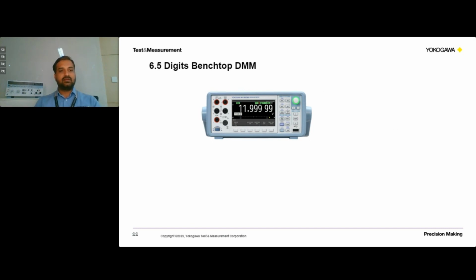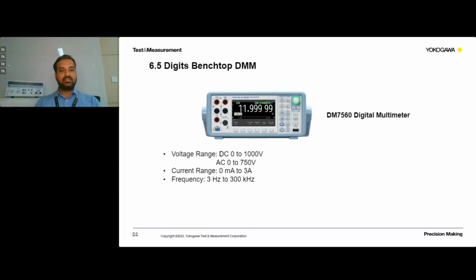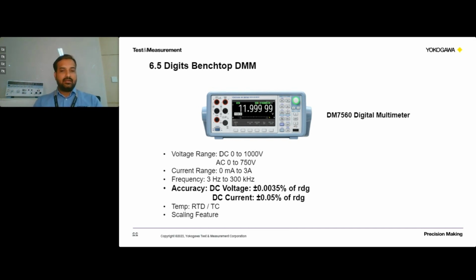Next, we have a 6.5 digit benchtop digital multimeter. The model number is DM7560. In this, we have a voltage range of DC 1000 volts and AC 750 volts, a current range from 0 milliamps to 3 amps, and frequency covering 3 hertz to 300 kilohertz. It has an accuracy of 0.0035% for voltage and 0.05% of the reading for DC current. It also has the capability to measure RTD in 2 wire, 3 wire, 4 wire combinations, and it can also take thermocouple input. And it also has a scaling feature.